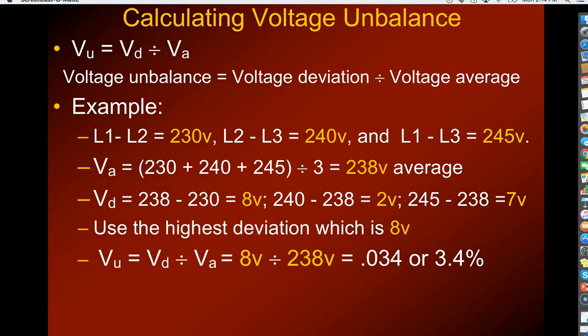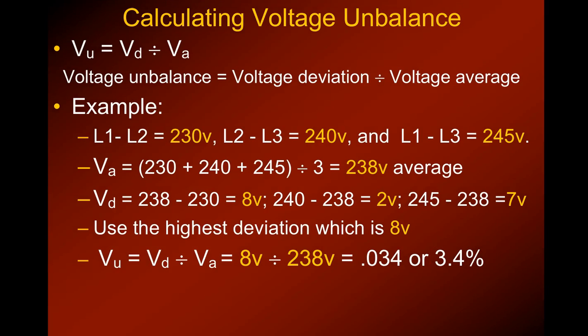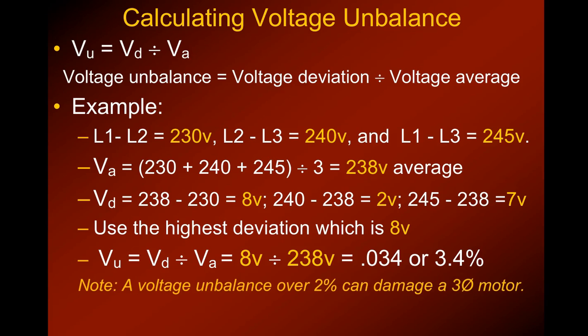So is that good or bad? It doesn't seem like much, but voltage unbalance over 2% can damage a three-phase motor. It will certainly overheat it and shorten its life. So if you run across a three-phase motor that has a voltage imbalance greater than 2%, you need to find out why that is.